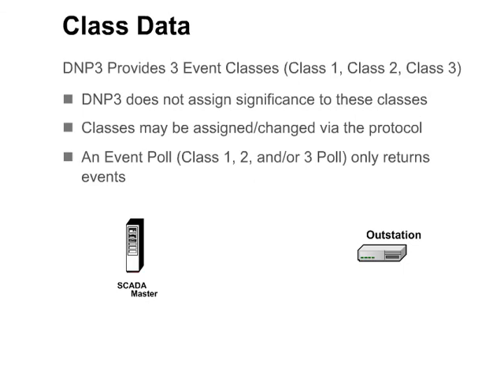The protocol specification does not assign any significance to the event classes. Some installations report binary input data in class 1 and analog input data in class 2. However, data can be assigned to the classes in any manner that makes sense in the system. Classes may also be assigned and changed via the protocol. An event poll — that is a class 1, 2, or 3 poll — only returns changes or events.